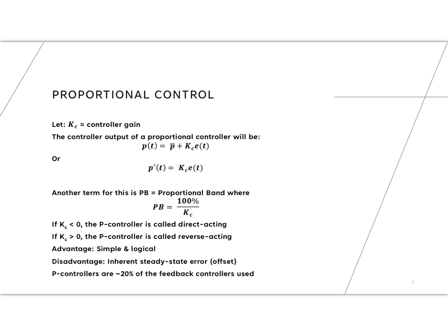So if we do it in terms of a change from the steady state, the constant value, so using deviation variables, the p(t) that we see right here, p'(t), that's my deviation variable. And most of the time in our textbooks, we're going to use controller gain, but when you're talking to people who do controls, they will often talk about it as being proportional band. Proportional band is basically the reciprocal of Kc as a percent, okay?